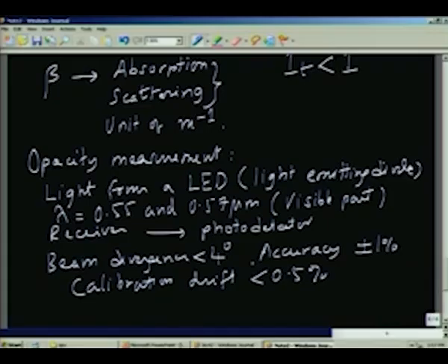So, we use a specific wavelength, therefore, this is very important to remember. If you use a different wavelength, the properties of the medium will be quite different. Therefore, when you are quoting the numbers, one must immediately see which instrument has been used, and what wavelength was used in that particular instrument. That is very important, because opacity is not independent of the wavelength of the source of radiation. If you use, for example, a helium neon laser, which has a higher wavelength than what I have given here, it will give you a different opacity.